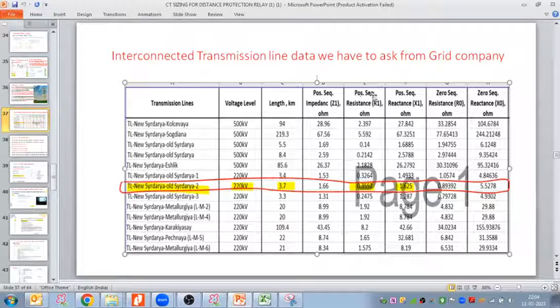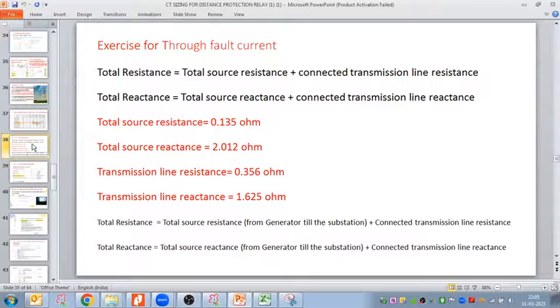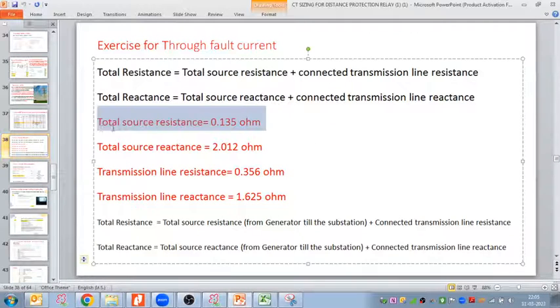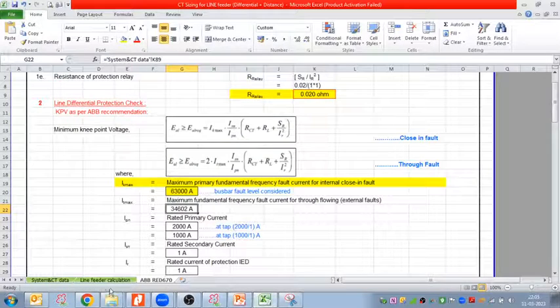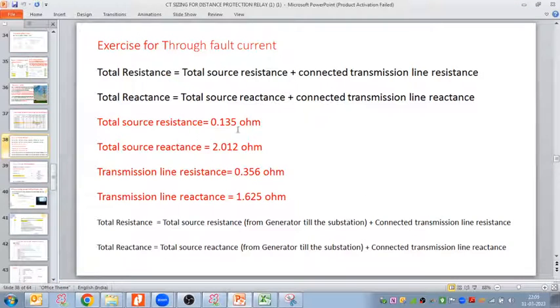Then the positive sequence impedance: positive sequence resistance 0.3552, positive sequence reactance X1 1.625 ohm, zero sequence resistance, zero sequence reactance, and impedance also we have, right? Now we need to add both the resistance and reactance to find the impedance at the fault point. For the through fault current, the total resistance till the fault point would be the total source resistance plus the connected transmission line resistance. Similarly, the total reactance is the total source reactance plus the transmission line reactance. The total source resistance is 0.135 ohm, which we just calculated, and the total source reactance is 2.012, 2.013 ohm.